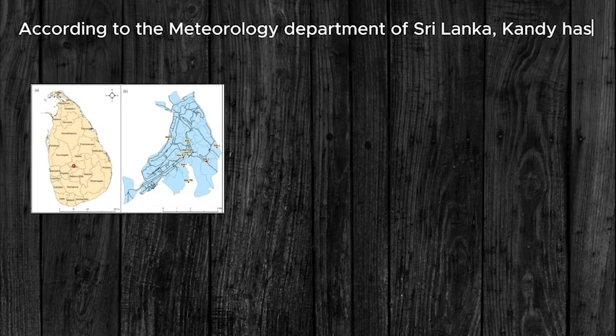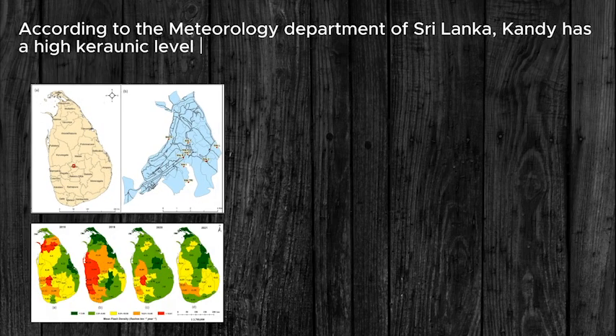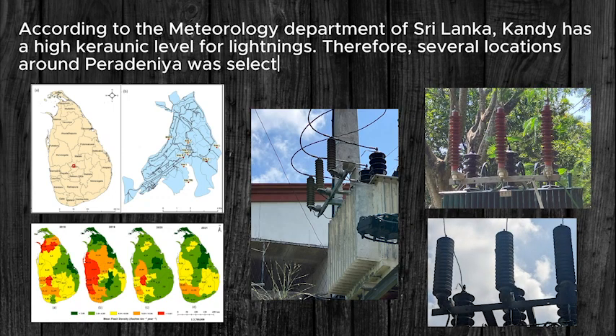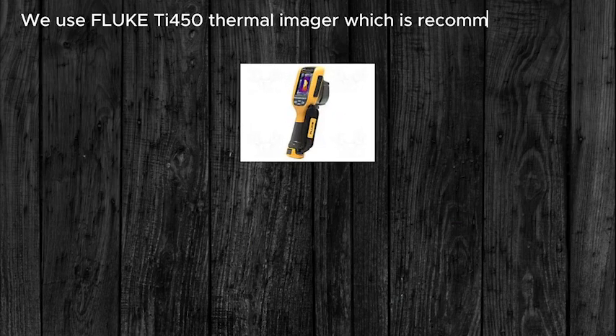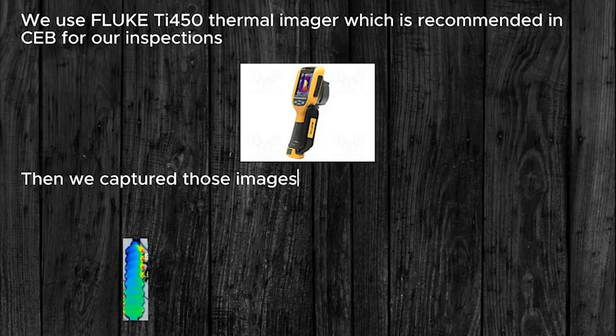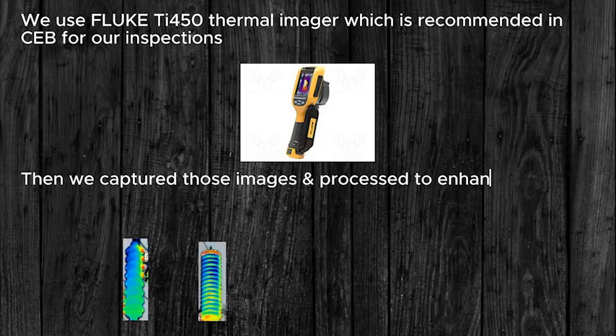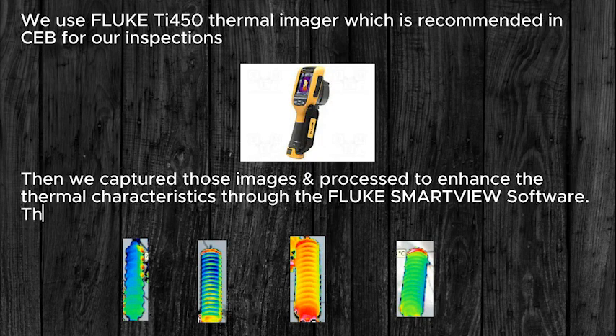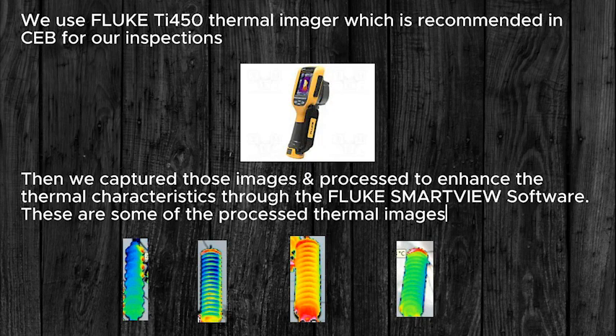According to the Meteorology Department of Sri Lanka, Kandy has a high keraunic level for lightning. Therefore, several locations around Peradeniya were selected for our inspection. We used the Fluke Ti450 thermal imager, which is recommended by CEB. We captured thermal images and processed them to enhance the thermal characteristics through the Fluke SmartView software.